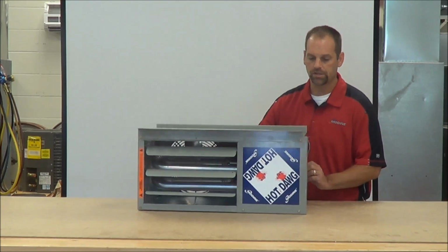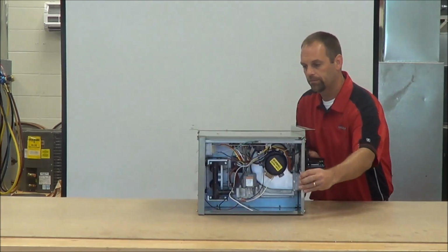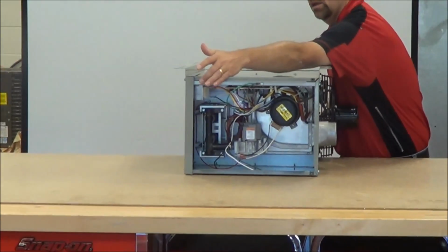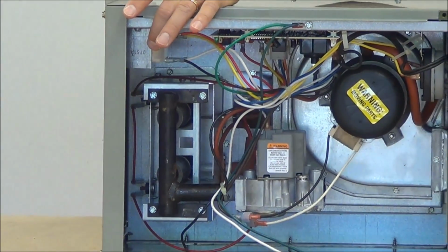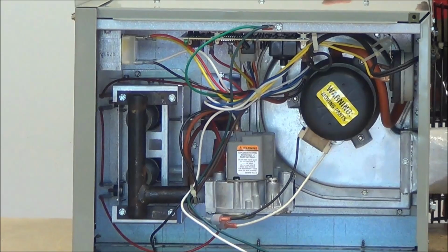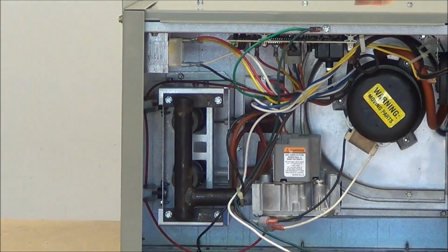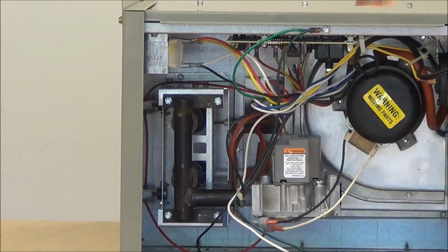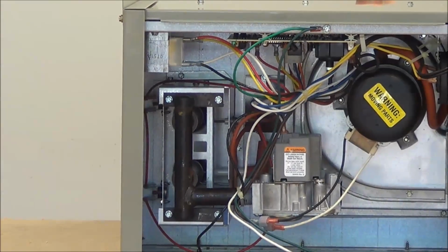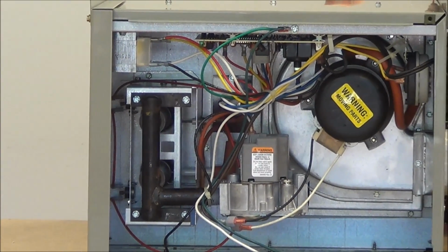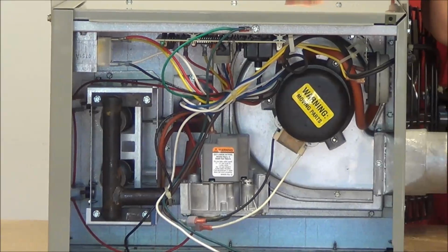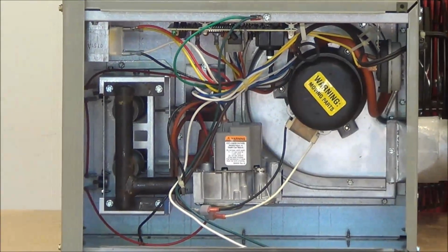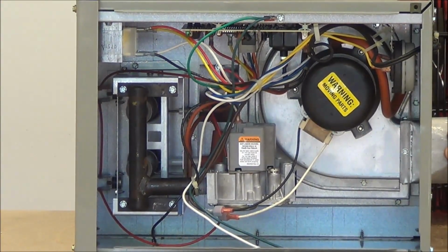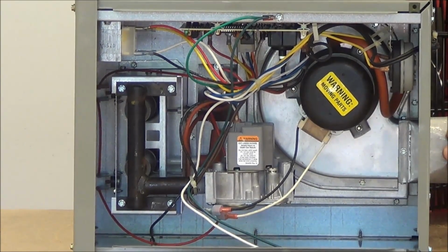So how to do that is, the transformer on this unit is located in this corner up here, and it has 4 wires running to it. It's got a low voltage side, which is 24 volts, and it's got a line voltage side, which is 120 volts. You're going to want to make sure, first of all, that your power is onto the unit. And to the one side of the transformer, you're reading 120 volts.